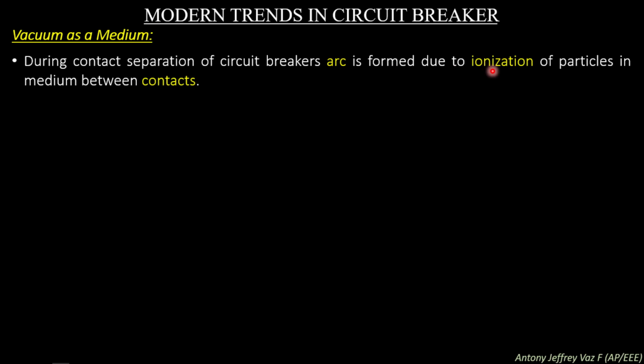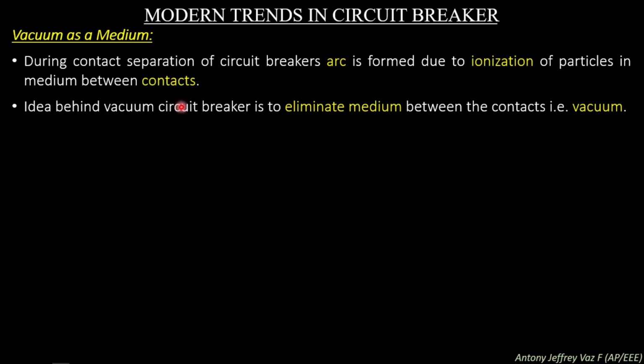During contact separation of circuit breakers, an arc is formed due to ionization of particles in the medium between contacts. So the arc which is created when a circuit breaker is opened is due to ionization of particles present in the contact space where the arc is initiated, where the moving and fixed contacts get opened. The idea behind the vacuum circuit breaker is to eliminate the medium between the contacts, that is, to create a vacuum. By eliminating the medium present between the contacts of the circuit breaker, a vacuum is created, and in this vacuum we separate the contacts, so the arc is going to be present in the vacuum.